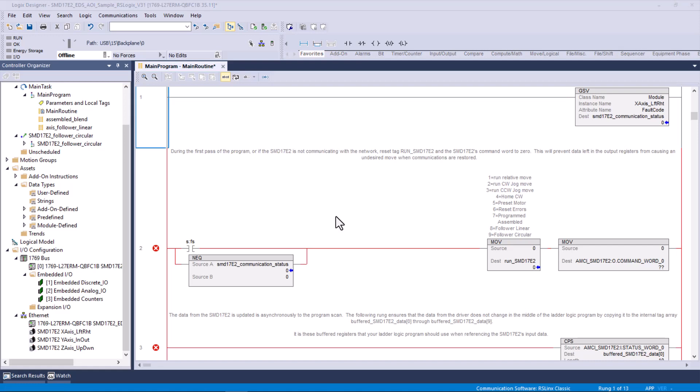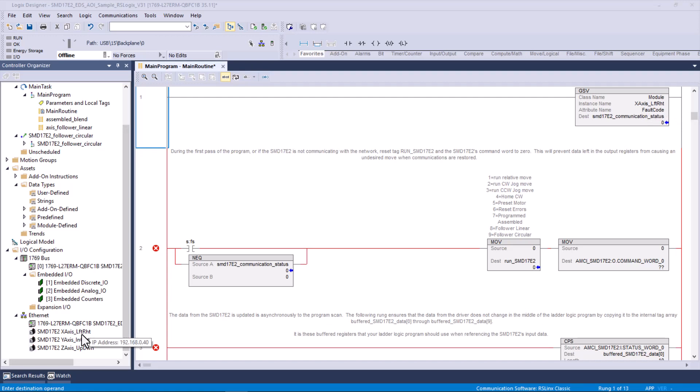One way to determine, because remember, this is a sample program. I did not create this. This is available from AMCI. So there's already logic written. All you have to do is replace the tags that aren't defined with something that is defined. So this tag up here, x-axis left right, that was from basically a module defined tag that I created when I added that SMD 17E2 to my project and named it x-axis left right. I took the class of objects, SMD 17E2, and I created an instance called x-axis underscore left right. And then I entered that here, and then this became a happy rung.